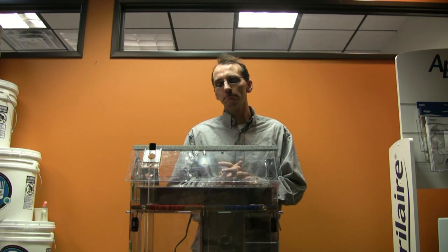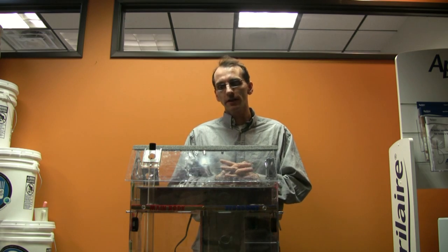Right. And just to throw a term out there, it's usually called an orphaned hot water heater. They get called an orphaned hot water heater because you take away the furnace and they're orphaned in the basement with an oversized duct. That is the technical term. It's an orphaned water heater. But they can really be an issue.